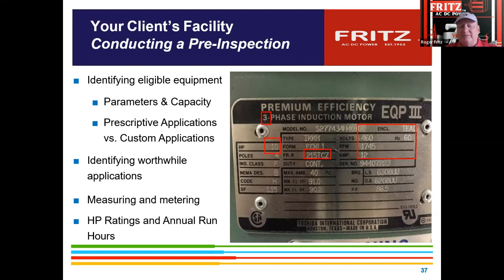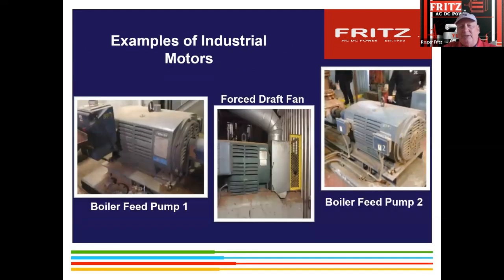But we've run into facilities where they went to bid, looked at the application, and got it all installed, everything to spec, but somebody didn't look at the RPM ratings. And now they literally cannot run those motors over 50 Hertz or they'll trip out all the time. They just have too much amp draw. And it caused a little grief. They're getting around it, but it's not the best way to do it.